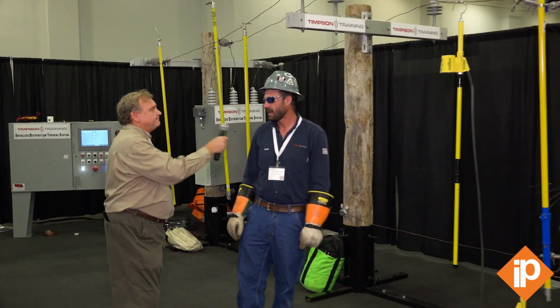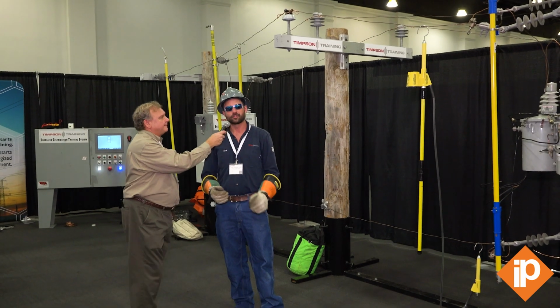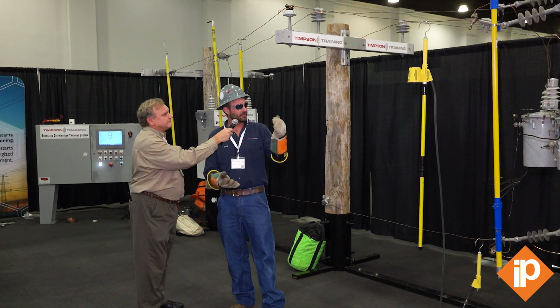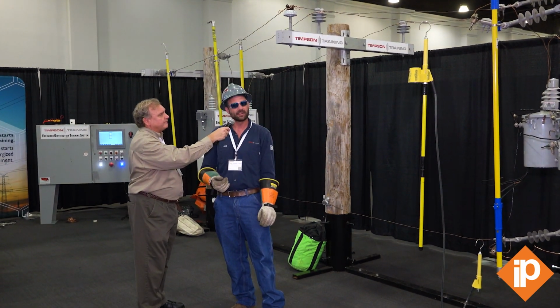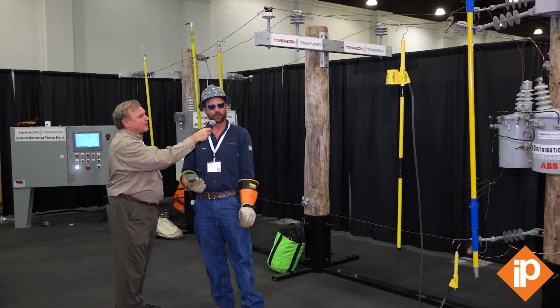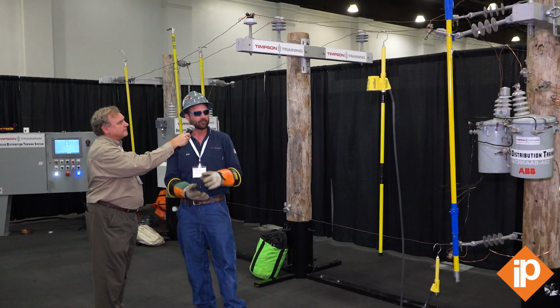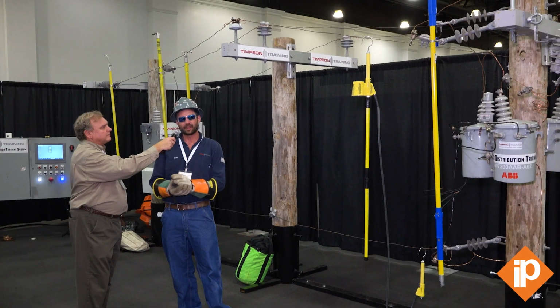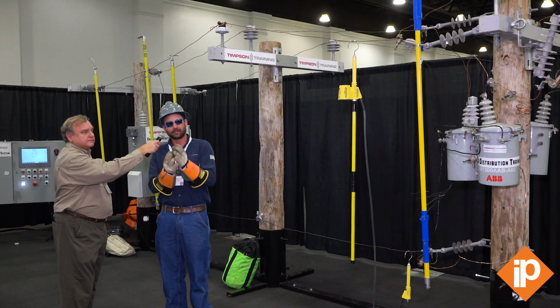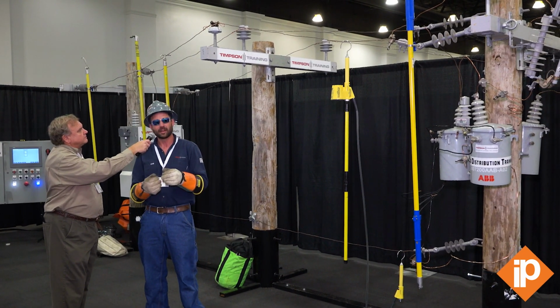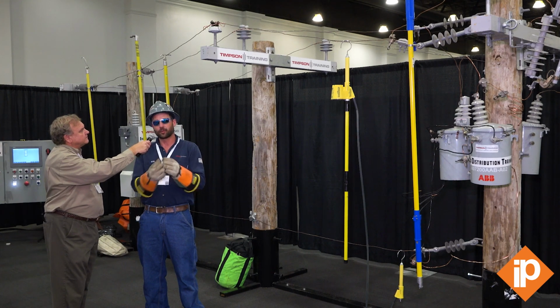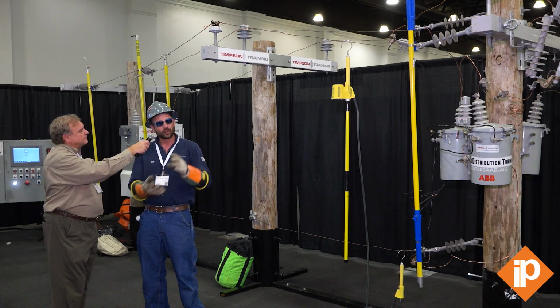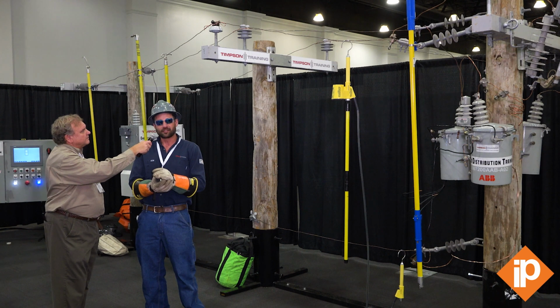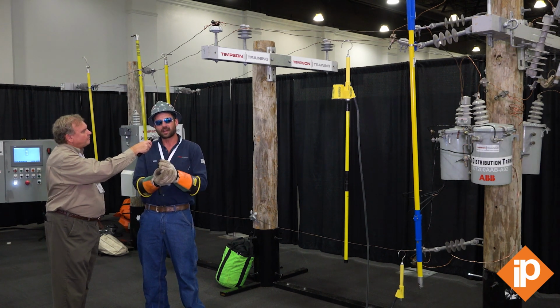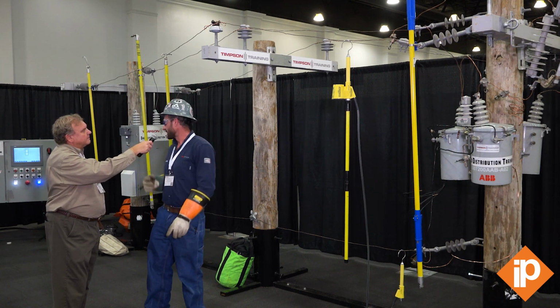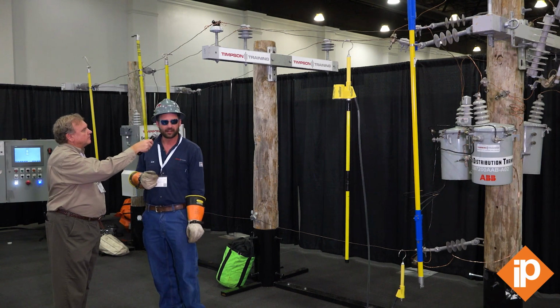Go ahead, Caleb. Yeah, so what we have here is a high voltage training system. This system goes up to about 14,000 volts phase to phase, 8100 phase to ground. The transformers are built in a particular way where they have a gap in the core. That gap is a bit flexible, so when you put a small load on the system, you don't get a huge voltage sag. And if you do get a voltage sag, we can adjust the voltages over there in that enclosure.